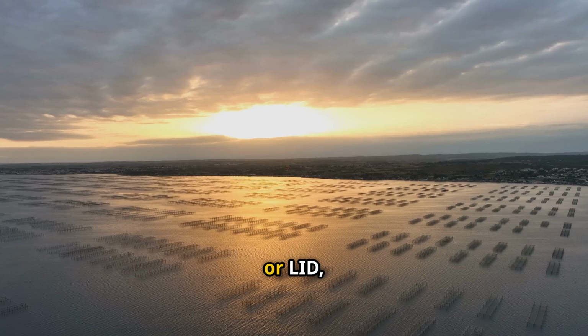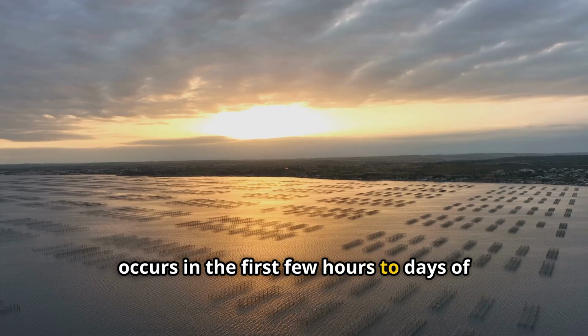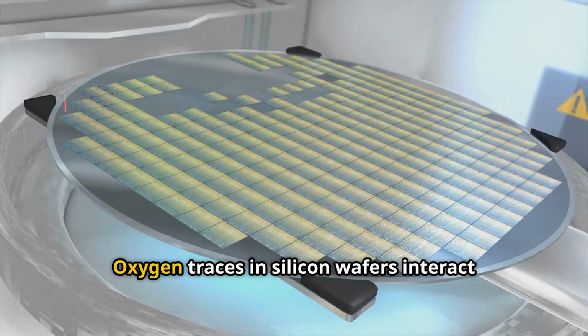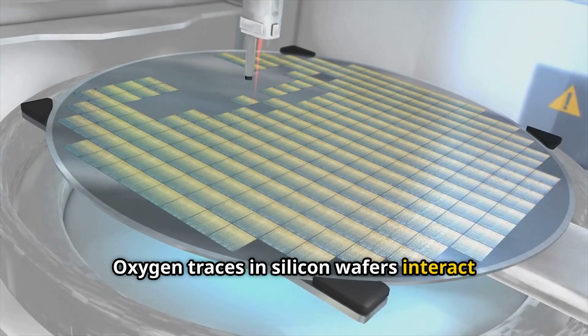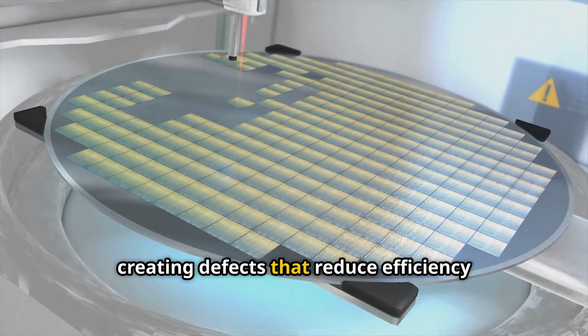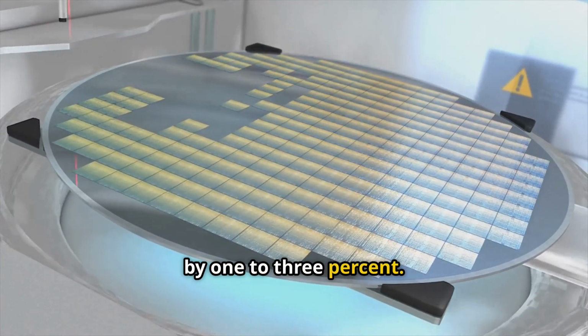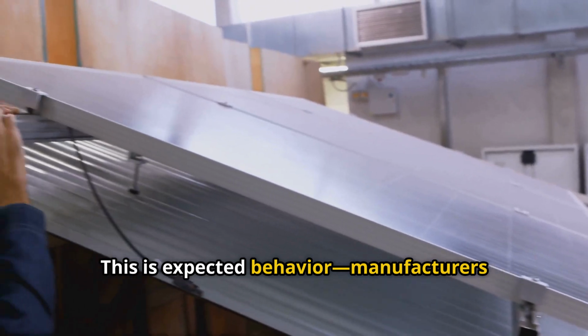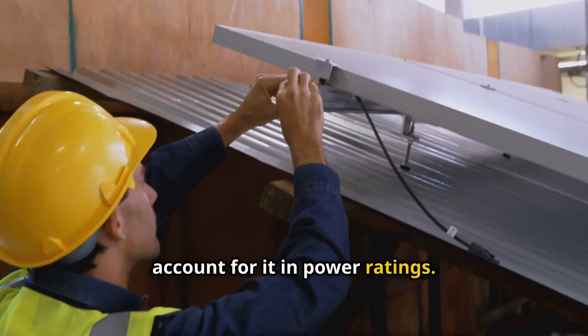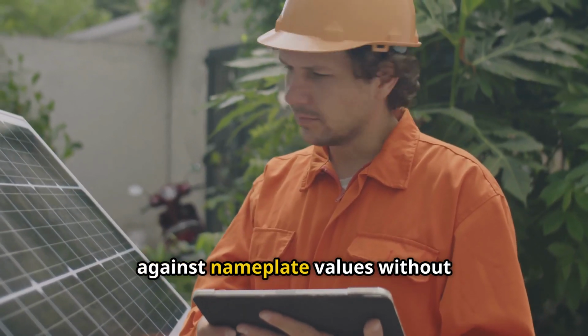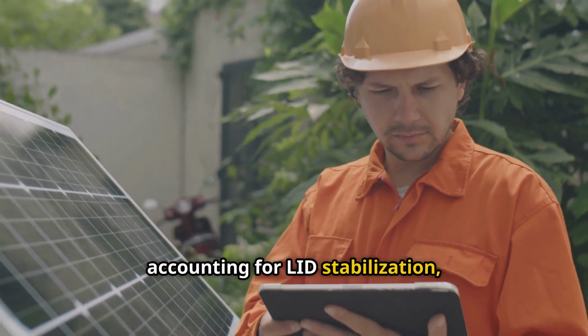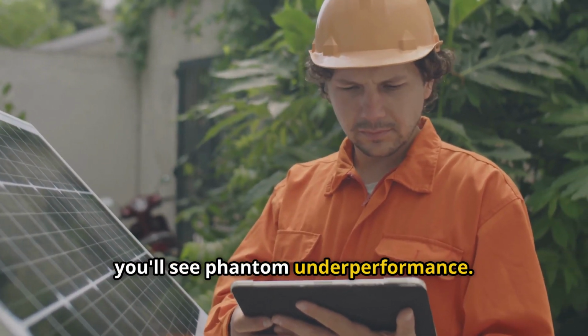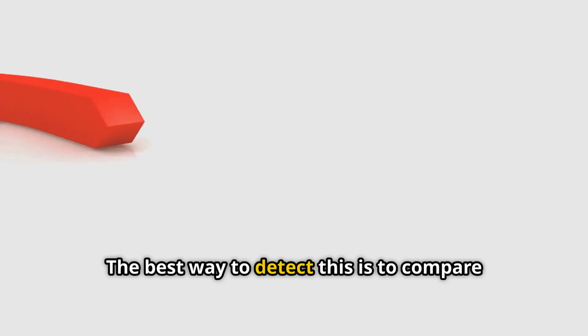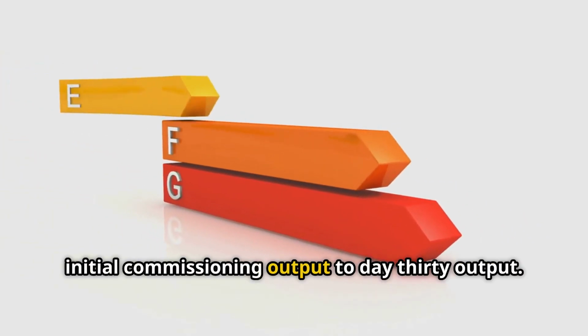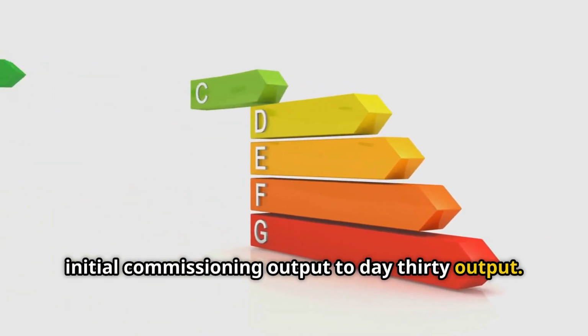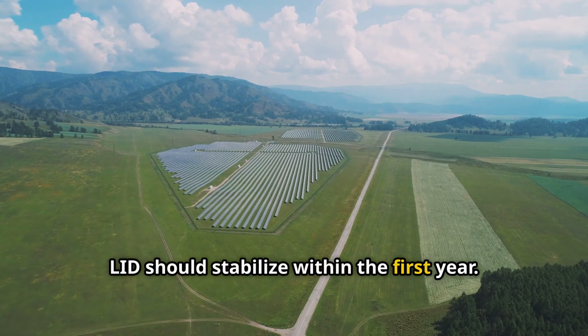Light-induced degradation, or LID, occurs in the first few hours to days of sunlight exposure. Oxygen traces in silicon wafers interact with boron dopant, creating defects that reduce efficiency by 1 to 3%. This is expected behavior. Manufacturers account for it in power ratings. But if you're measuring performance against nameplate values without accounting for LID stabilization, you'll see phantom underperformance. The best way to detect this is to compare initial commissioning output to day 30 output. LID should stabilize within the first year.